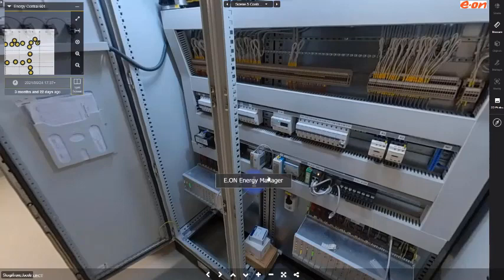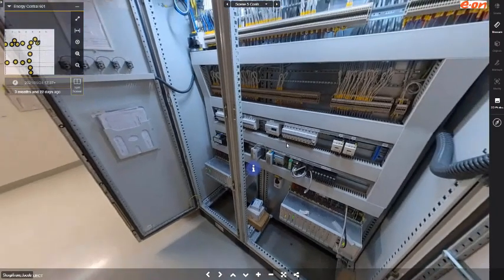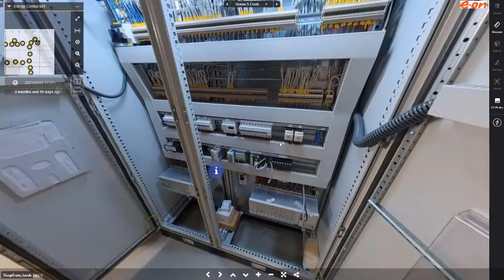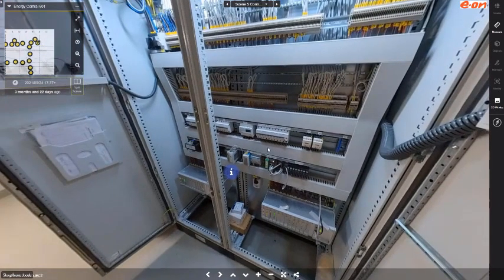When connecting a new building, we agree on a certain set of signals that needs to be passed through, and this is programmed with PLC coding. This way we have the possibility to communicate with the building and place suggestions on how to run the system optimally. It's not being forced, it's only recommendations. If it accepts, fine, and if it has something else to do in this building that is more important, it will deny the request.